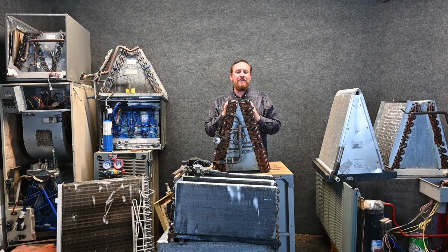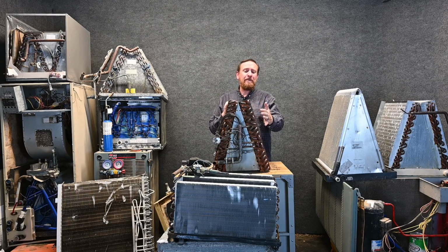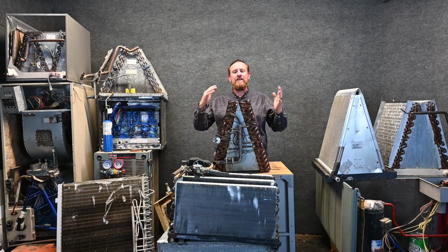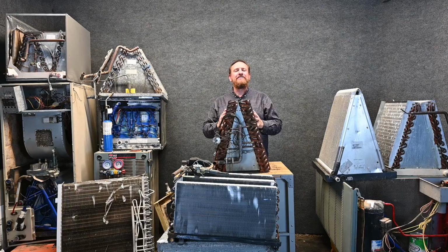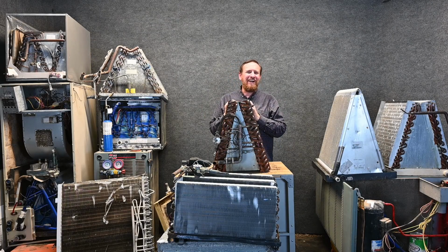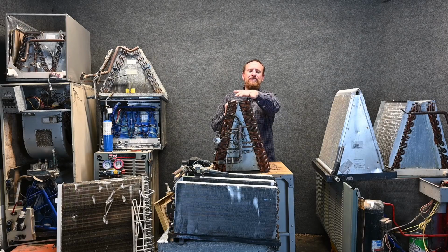So that's why a lot of people, myself included, typically when we come to an evaporator coil that's leaking, say, hey, you need a new evaporator coil. And many times, now that we have multiple different refrigerants out, you're going to replace the entire system so it's all a match set. We'll get into those details later as well. Still lots and lots to learn. So refrigerant leaking is a big one. That's what we're looking at replacing the coil.